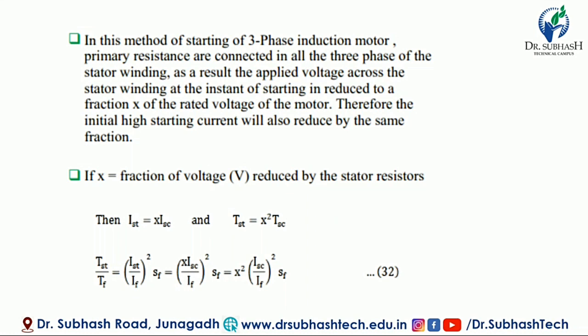If X is the fraction of voltage reduced by stator resistance, then IST (starting current) equals X into Isc. And the starting torque equals X squared into T short circuit torque.